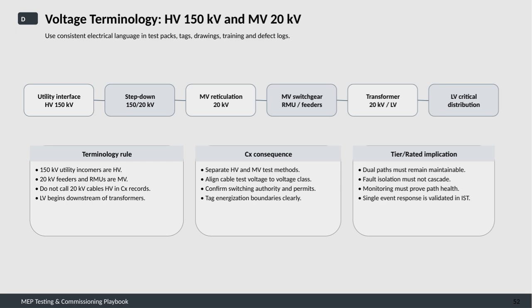In terms of commissioning consequences, this clear distinction means that we apply different test methods for HV and MV systems, align test voltages with voltage classes, confirm switching authority and permits before work, and clearly tag energization boundaries for safety and clarity. Finally, regarding tier or rating implications, maintaining dual paths must allow for proper maintenance without cascading faults. Monitoring must reliably verify the health of these paths, and single event responses should be validated during the integrated system testing phase. Overall, clear and consistent use of voltage terminology is crucial for safety, efficiency, and effective commissioning of electrical systems.